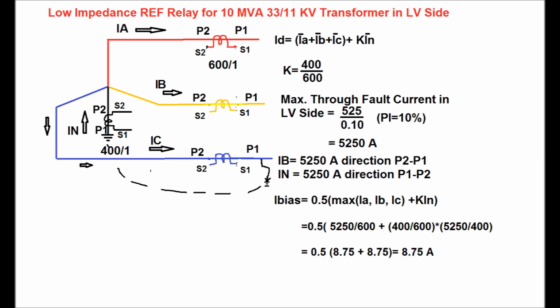Now under this condition, what is the value of the bias current? Bias current is given by 0.5 into the maximum of IA, IB, IC. Here the blue phase current is maximum, that is, here the blue phase means IC plus K into IN, and the blue phase current in terms of secondary value comes as 5250 divided by 600. Here the value of K is 400 by 600 and IN is equal to 5250 by 400. So the bias current comes as 8.75 ampere.